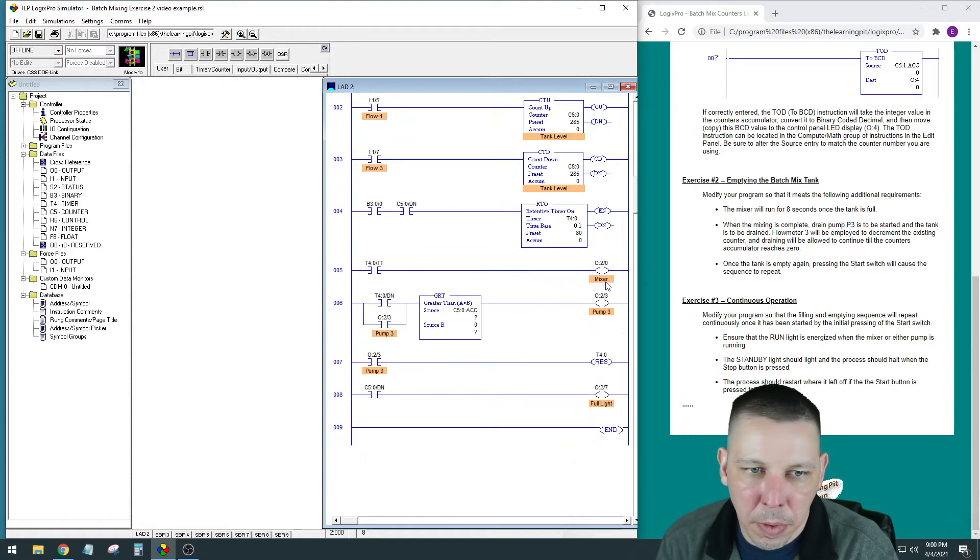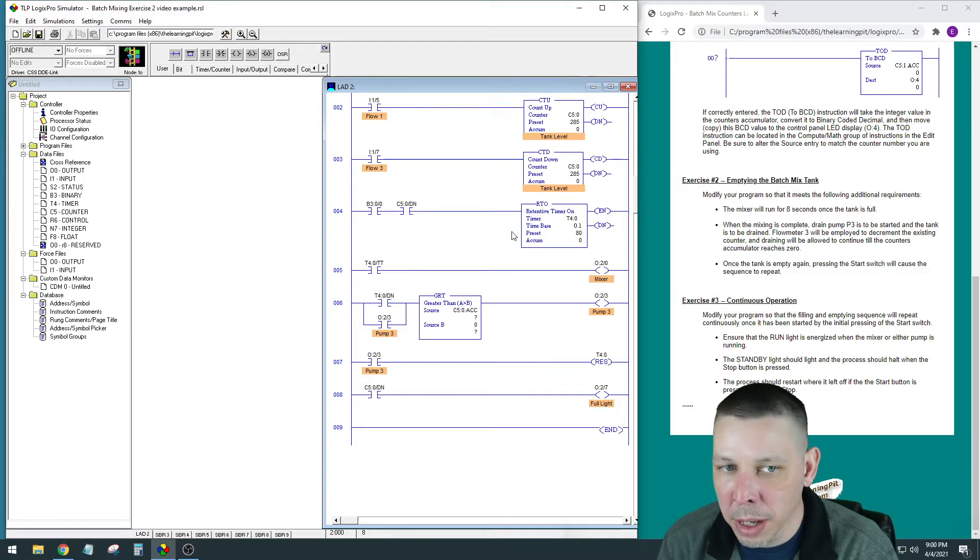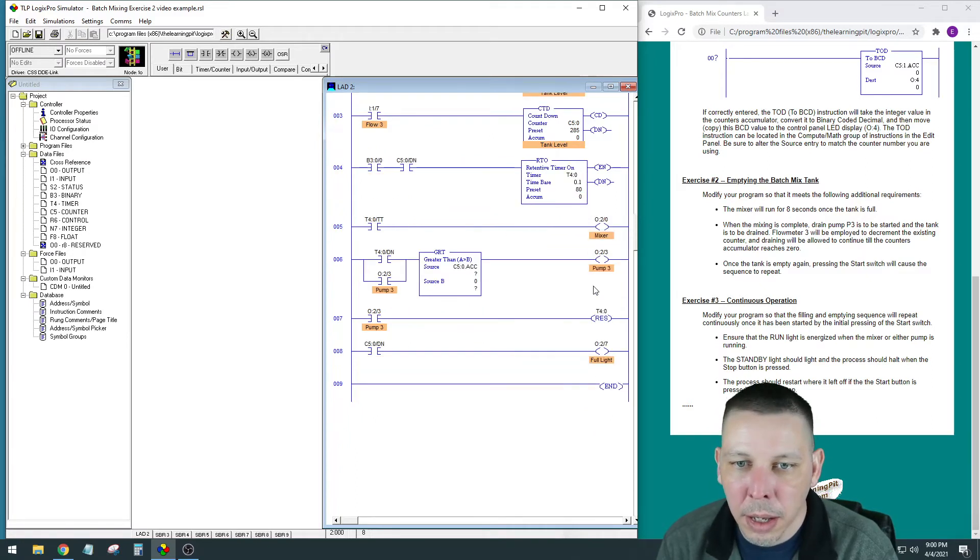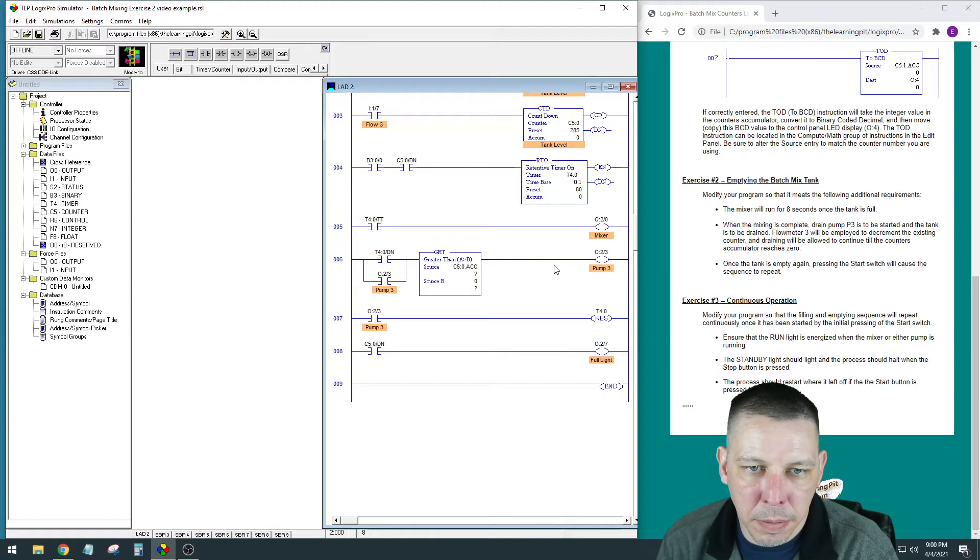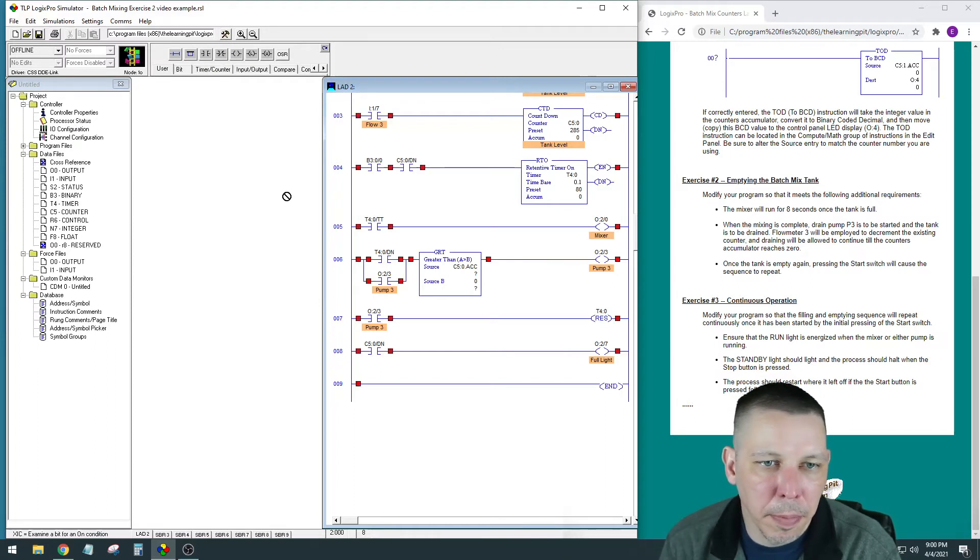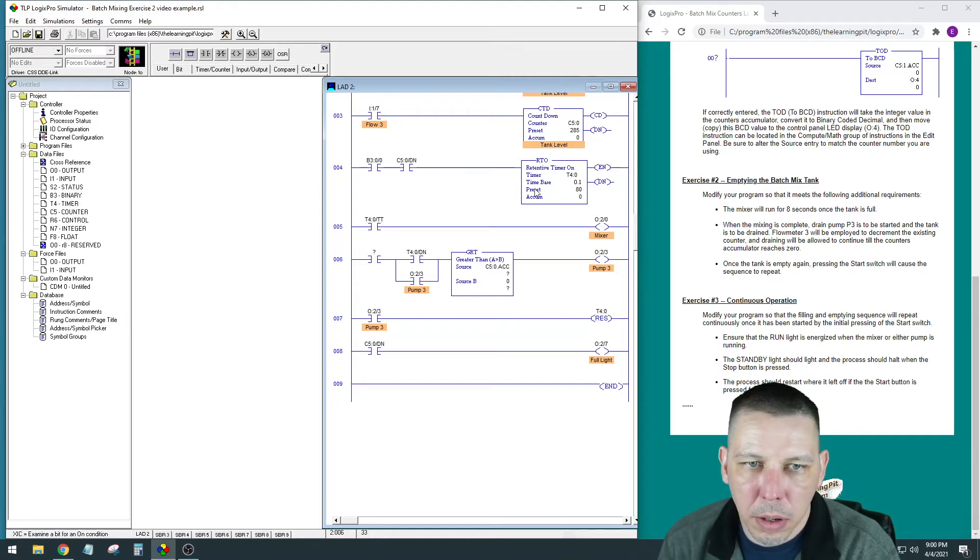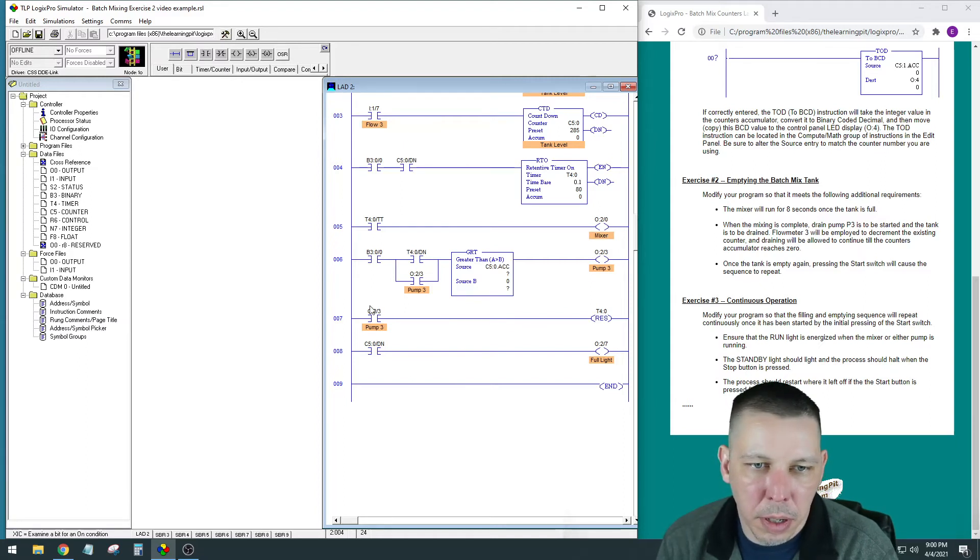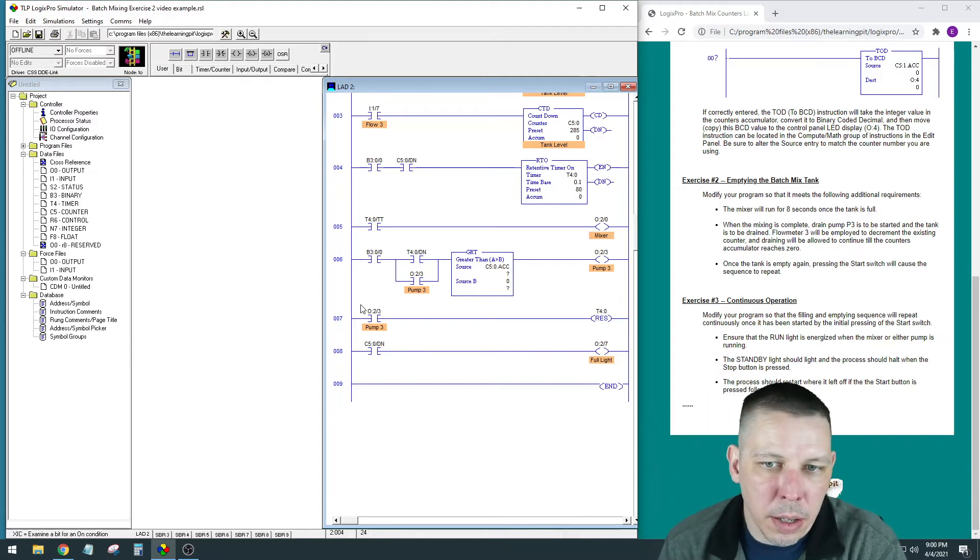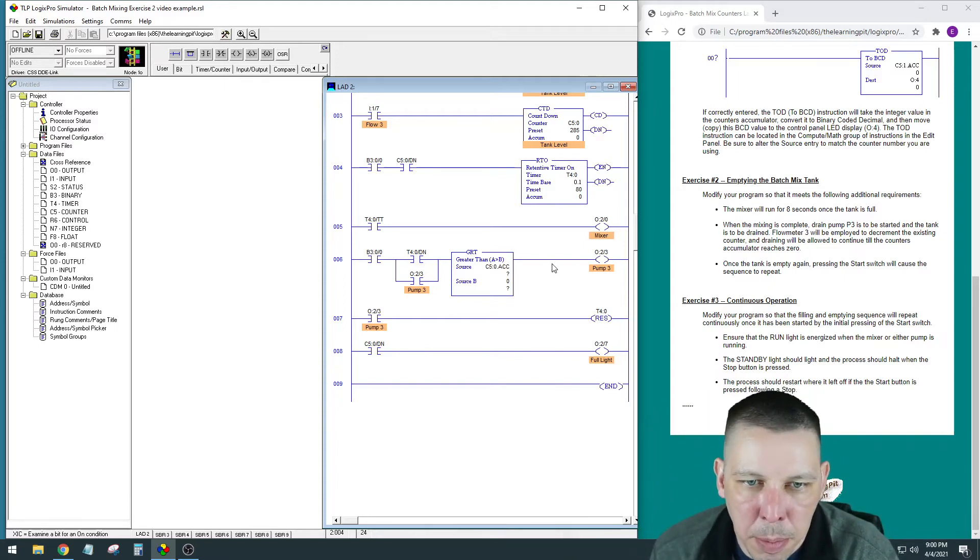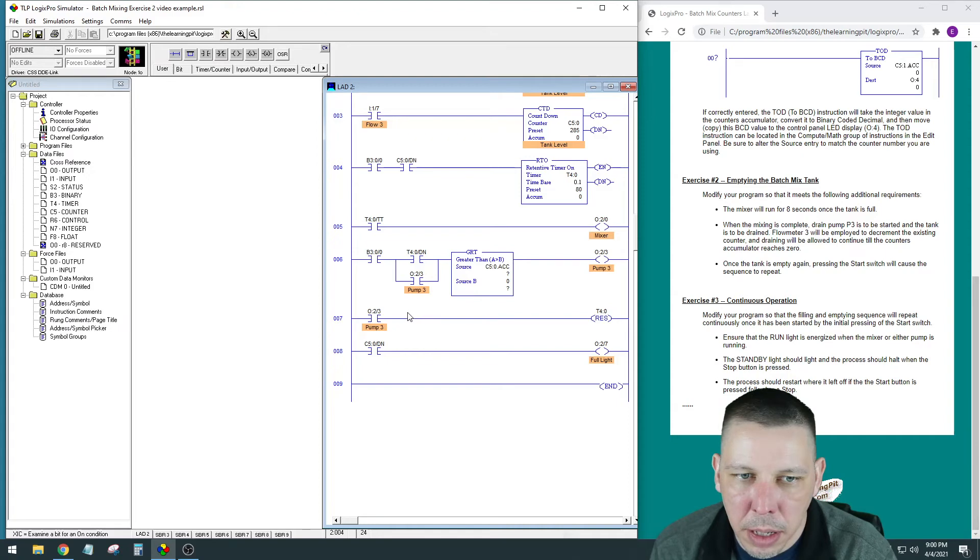The mixer—yeah, that's not going to need anything because the mixer output's only turned on when this timer is actually timing. So when this opens up, the timer won't be timing. The T4.0 done bit latches itself in. We are going to need something here—we're going to need the same thing we have there. This pump 3 we're going to interrupt, and is that going to work? Because if we stop pump 3 when it's pumping out, we de-energize it, then our latch is going to drop out.